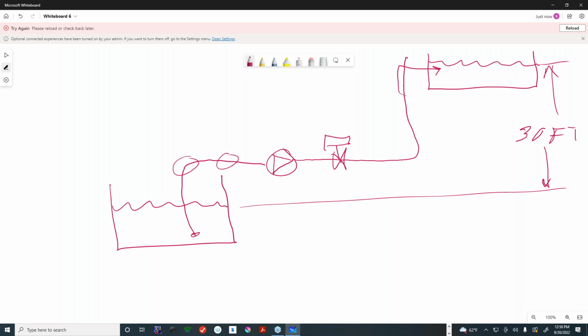And to clarify or to reiterate, in an HVAC hydronic closed loop system, the height doesn't really come into play per se, correct? Not in terms of the pressure differential required by the pump. The height becomes more of an issue in terms of the total pressure in the system if your pump or equipment happens to be at the lowest elevation. What is the pressure as a function of the static height plus the pressure differential of the pump? That has more to do with the design operating pressure than the pressure drop calculation. But to your point, if it's a closed loop pressurized system, we do not take into consideration the height of the fluid for the pressure drop calculation, only in open systems.